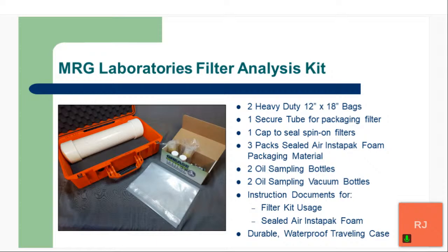And then there's also the case of a customer who was waiting to ship, and somebody else came along and threw away the filter. So that's also a benefit of having a kit like this, that you have something there that's ready to go. It's part of the procedure that we talked about for how we address filter failures or just any failure in general. If you have this kit, you're able to grab the kit, get the filter, put everything inside of it, and ship it right out that day. Versus if you have to grab something, put it on a desk, somebody looks at it for a couple of days and goes, okay, we don't need this dirty filter sitting here anymore. Let's get rid of it.